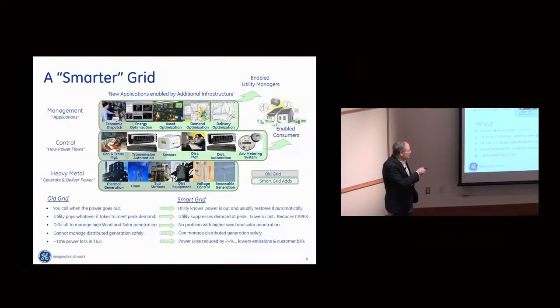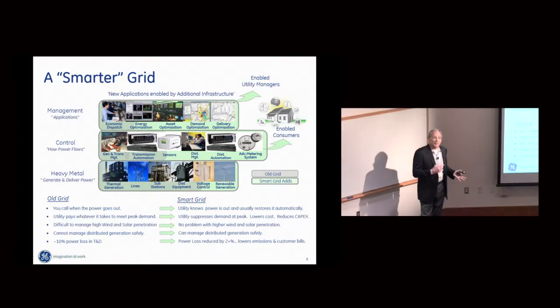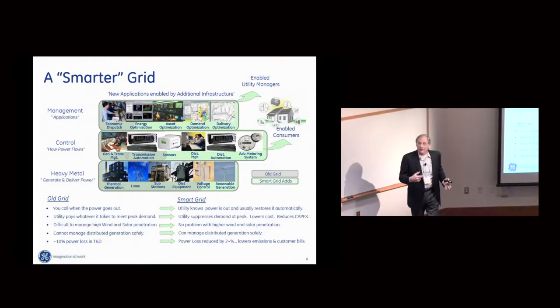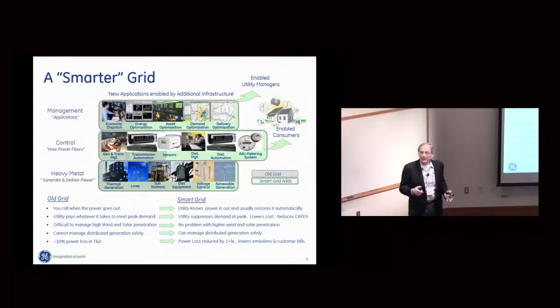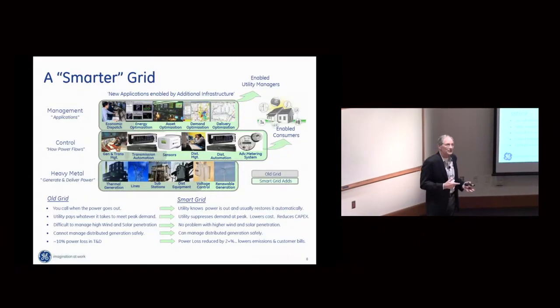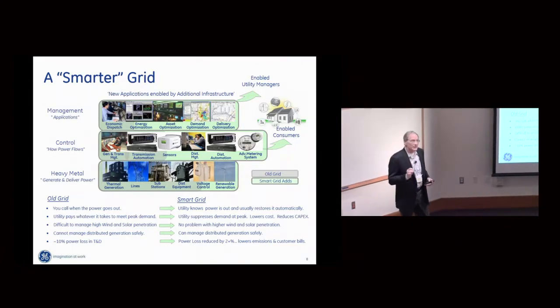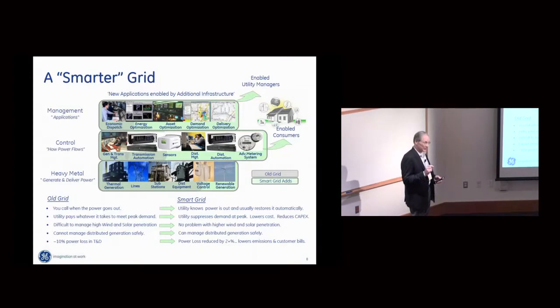We're putting more sensors right out onto the grid. This example is a sensor I can put on a transformer, and it can monitor in real time the oil of the main tank and look for up to 9 different gases dissolved in the oil. In the presence of ethylene or acetylene, each of those gases indicates a specific failure mode occurring in the transformer. Of course, then I look at the rate of change.